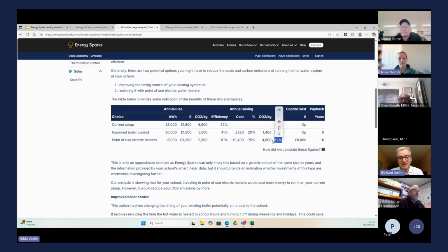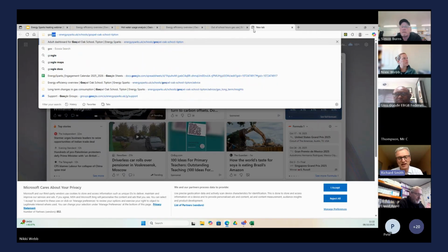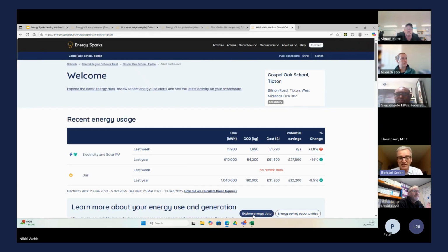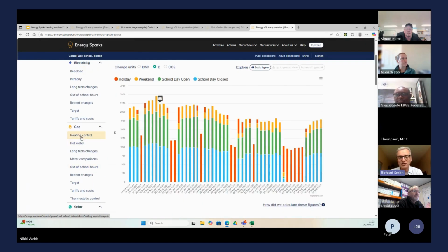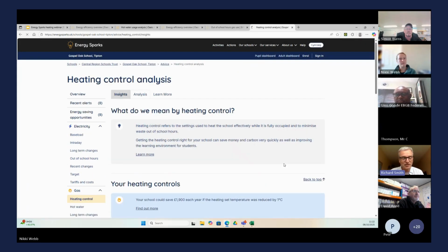Hot water is an area where you can save a lot of money. I still see schools now where it's on 24/7, 365 days a year, because we're so risk averse in our schools — understandably, I'm a chair of governors myself, I get it. But 60 degrees for an hour a day kills Legionella, so if you can sensibly heat your tank, whether it's 500, 300, or 500,000 litres, a few hours before you need it, you're good to go.